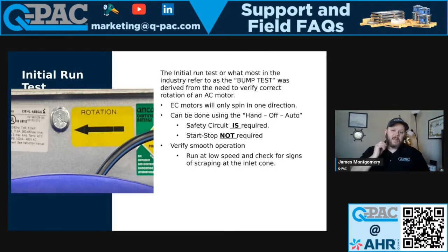Typically in the electrical world, we call the first run test the bump test. The reason we call it the bump test is that for typical AC motors, you needed to bump the motor to ensure you had the correct rotation. If you didn't have the right rotation, you'd flip two phases and achieve the right rotation. An EC motor does not need phase angle direction or the correct phases to be in a specific place. So A, B, C, they're all hypothetical. The EC motor is only going to spin in the direction that it's been told to spin.